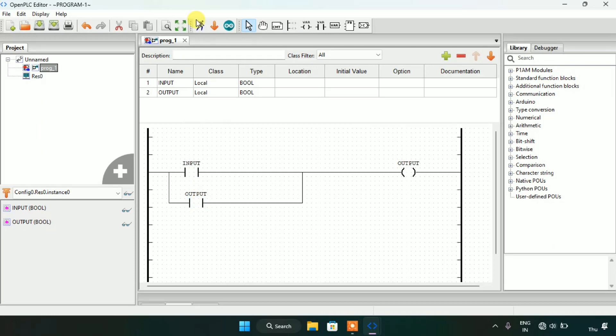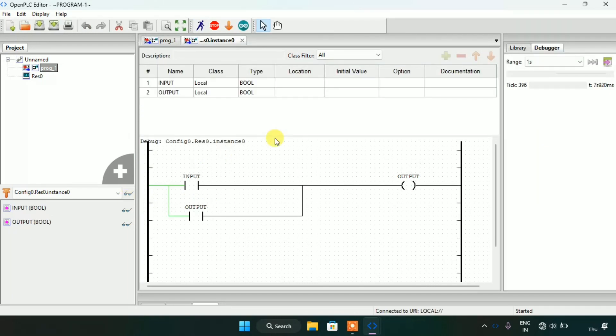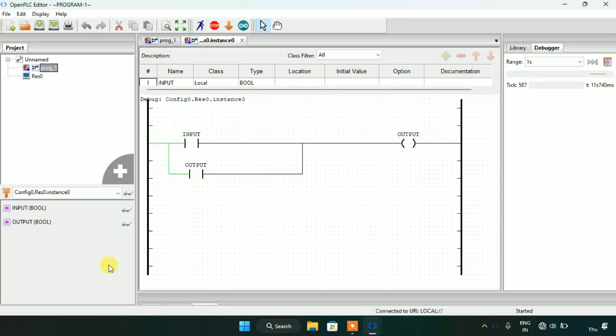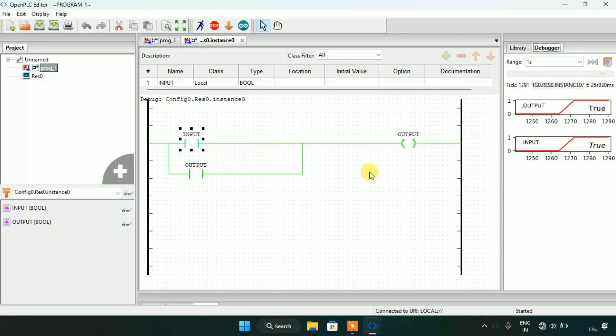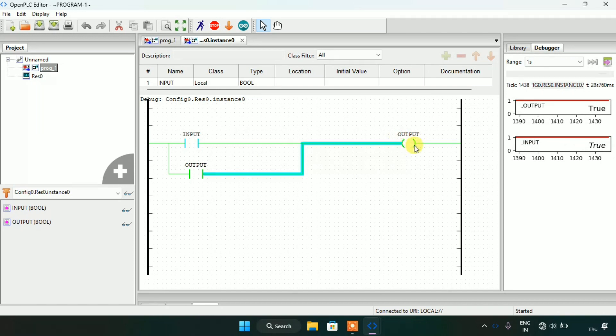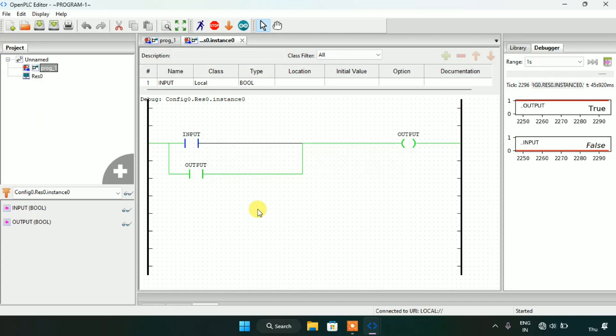Now let's start the simulation and see what will happen. The simulation is complete and I will click on the debug glasses. Then after I will show you the output and the input. As you can see when I force the input to true, the output will go true. As the output goes true, the normally open contact which I latched — addressed as the output — will also go true. And when I modify the input as false, you will see that the output is still true. This is how we make a push button.